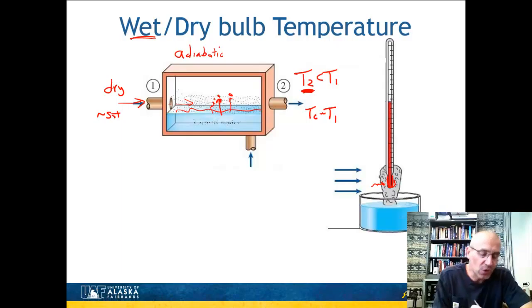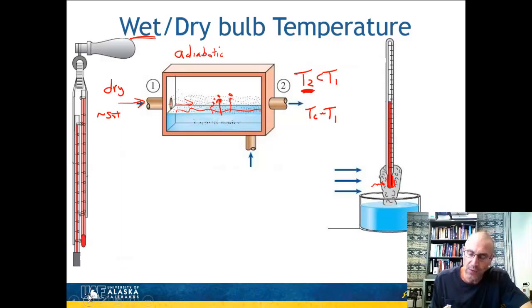And the practical way to do this, because this is a measure of how dry the air is, which is ideally what we want, is something called the sling psychrometer, which I show here on the left. You have two thermometers. One is just sitting there, recording the actual air temperature. Over here we have that wick, or sponge, that we add water to. Then we spin this thing around in the air to force air through it. This thermometer on the left-hand side is going to be somewhat less than that on the right, because the larger the difference, the drier the air is.